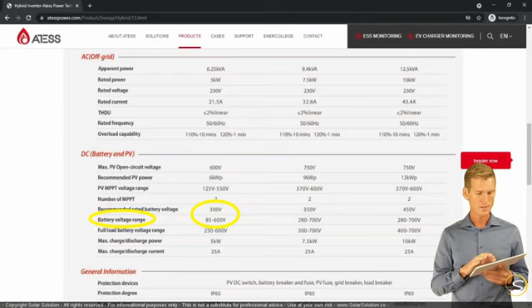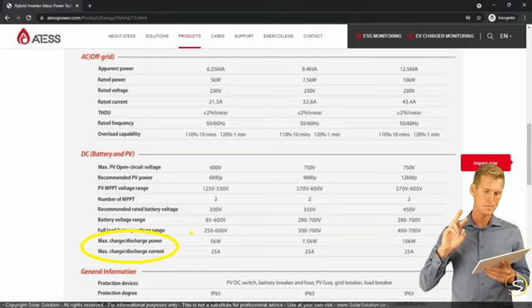Then you can see here a little bit lower, the values for the connection between the hybrid inverter and the battery bank. What is quite important to notice is that it says that the minimum battery voltage should be 85 volts. So it is a relatively high voltage battery bank, which is no problem, but it's just important to be aware of. And it says here that the maximum charge current is 25 amps. So they have 2 values. They say either way it's a maximum of 5 kilowatts or a maximum of 25 amps, which then suggests that it's more advantageous for you if you use a battery bank with a relatively high voltage.